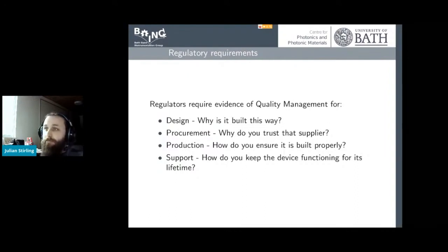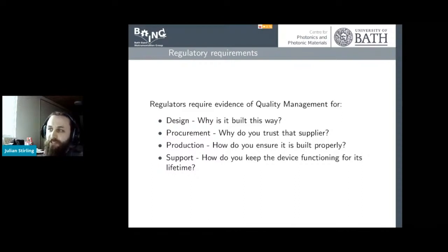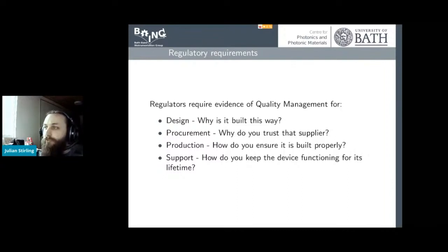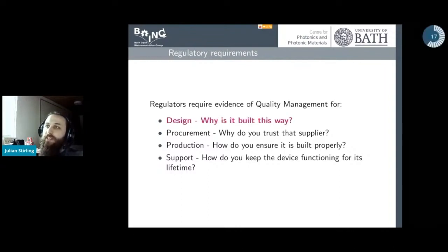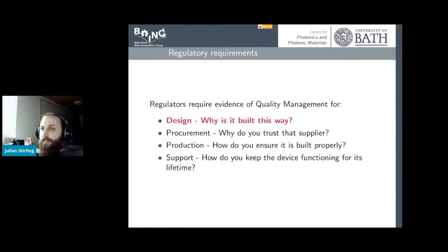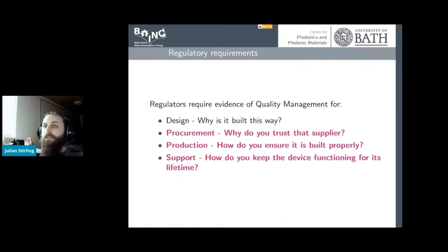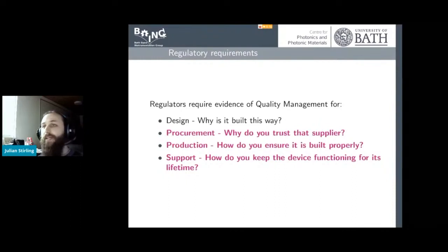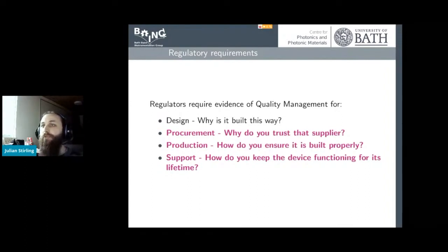The QMS also covers procurement — why did you trust that supplier, are you going to get the same part every time? It covers production: how can you ensure it's built properly, not just the one you tested but every single one you produce? And it covers long-term support: people are going to need feedback, support, and there's a process to deal with complaints. For us, we're mostly thinking about how to do the quality management system for something that's open source and community-based. If you want an open source design produced in lots of places, you can't do all of this for people — they'll have different procurement in different countries, different production facilities, and slight design variations. You need to collect all of this information together to help a manufacturer actually produce something.